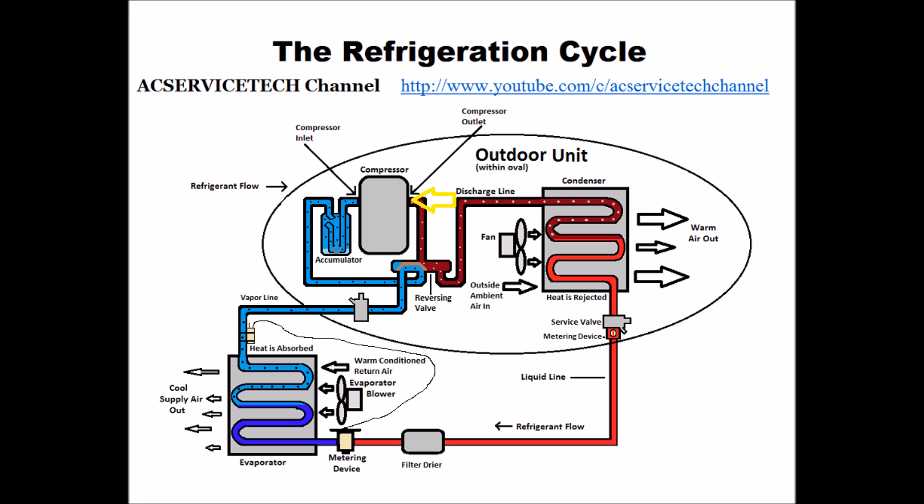This point is called the discharge line. It then goes through the reversing valve and is still considered the discharge line — it's the high pressure, high temperature vapor refrigerant. It then goes into the outdoor coil, which in this case is the condenser coil because we're in cooling mode.